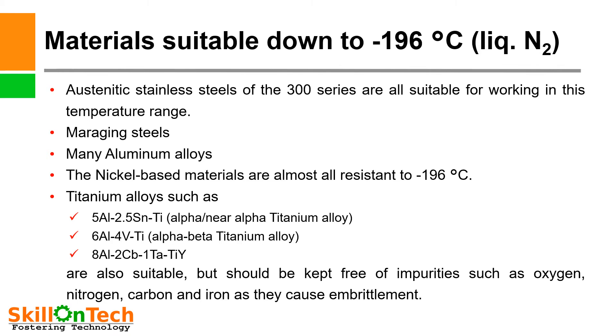Materials suitable down to –196°C, such as for liquid nitrogen which boils at –196°C. Austenitic stainless steels of the 300 series are all suitable for working in this temperature range — for example SS304, SS316, or SS321. Marraging steels are iron alloys known for possessing superior strength and toughness without losing ductility. These steels can also be used for high temperature service up to 480°C, have very good improved strength, and are used for gas turbine engine casings or aerospace structural members.